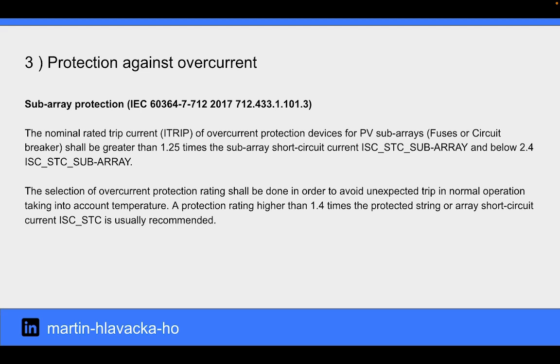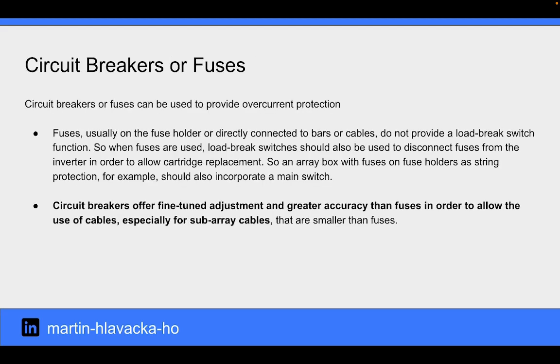The selection of overcurrent protection rating should be done to avoid unexpected trips in normal operation, taking into account temperature. A protection rating higher than 1.4 times the protected string or array short circuit current is usually recommended. Circuit breakers or fuses can be used to provide overcurrent protection.